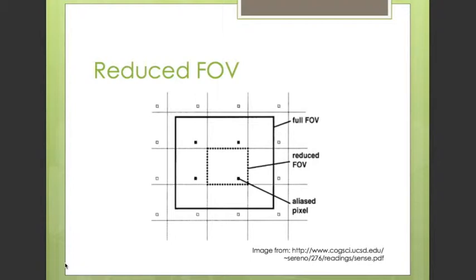As seen in the figure, signal separation must take place in order to remove the effects of the surrounding points. In this step, the sensitivity encoding comes into good use. For each single coil, the signal superposition occurs with different weights according to coil sensitivity. The coil sensitivities, calculated and mapped beforehand, apply a different weight to every position. The sensitivity mapping can be demonstrated by the image below.